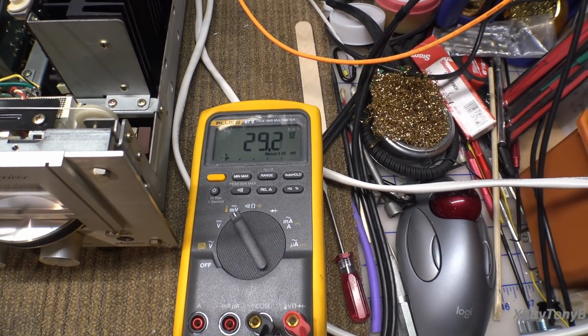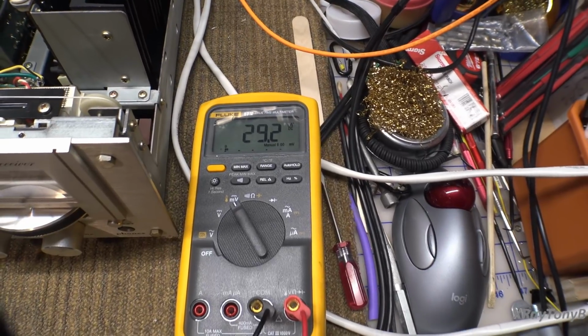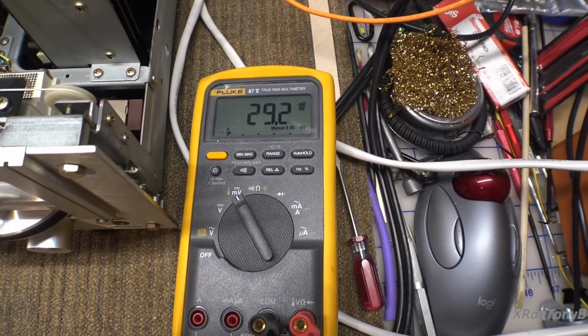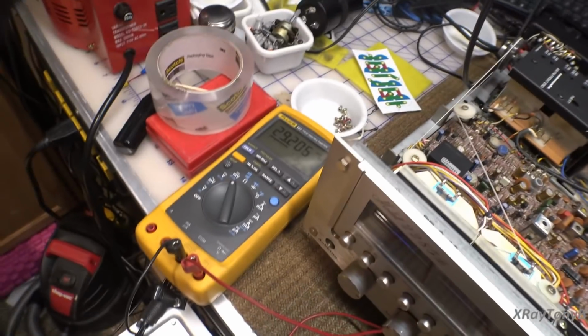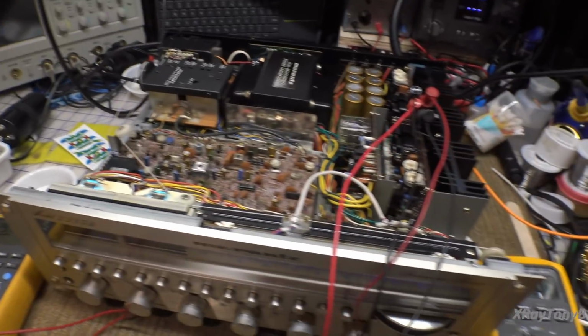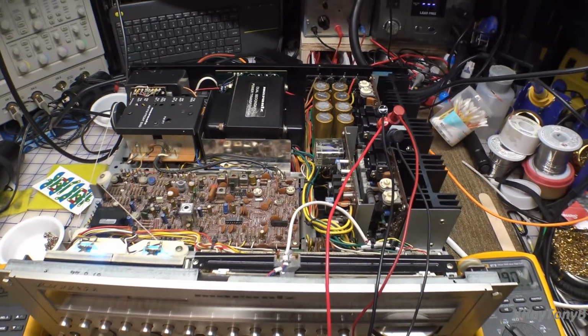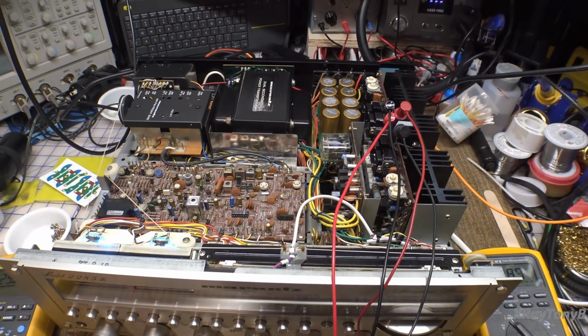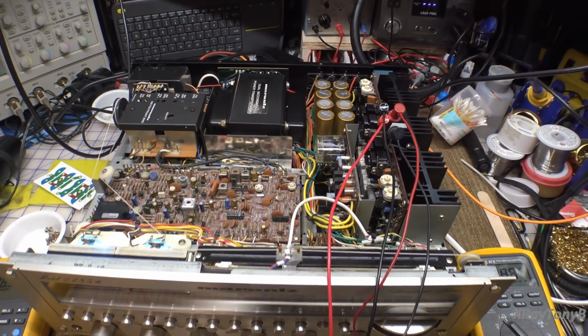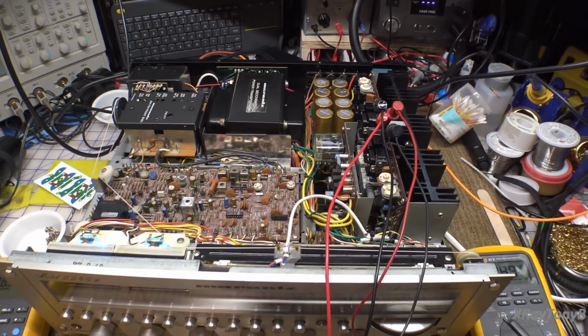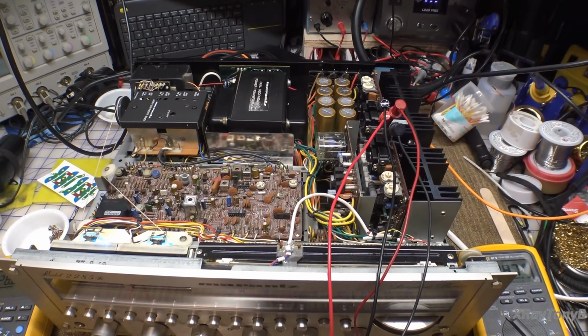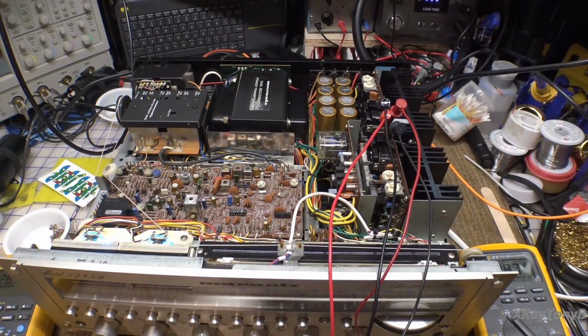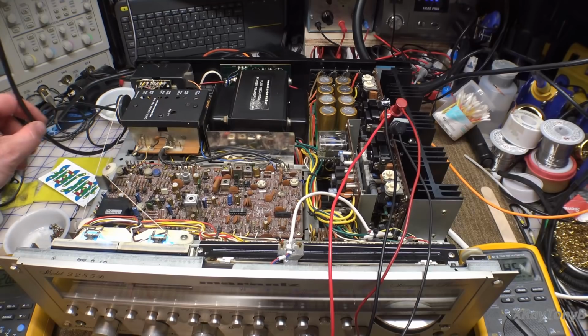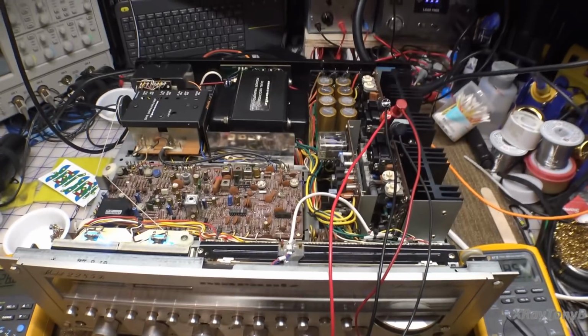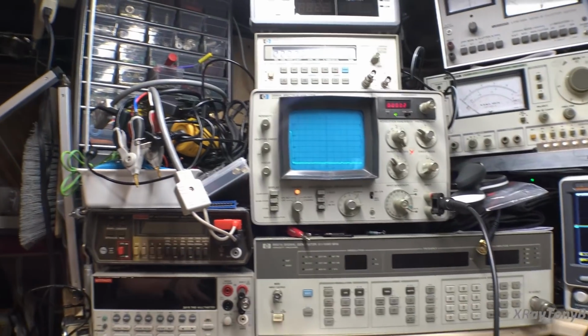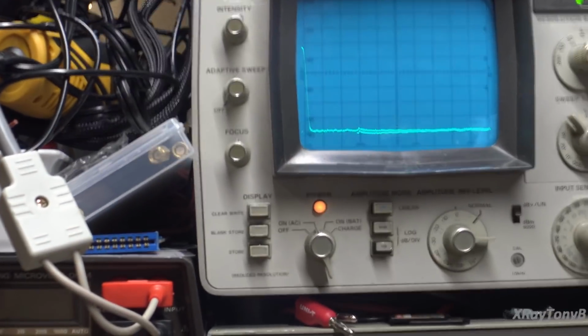Okay, the first thing we did was just made sure that we went by the book and we set the bias to be 30 millivolts. And you can see we're pretty close on both channels. And we also went through and verified DC offset once again to be 0 volts, and it was 0.2 millivolts, something like that on both channels. It was staying within plus or minus 1 millivolt on both channels. We had it. So everything is properly calibrated, yet we still have this really strange distortion.